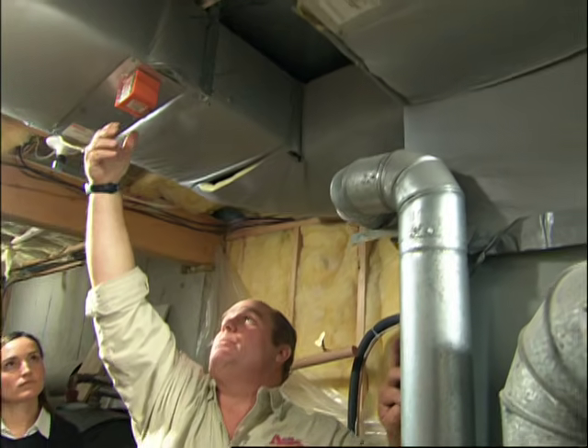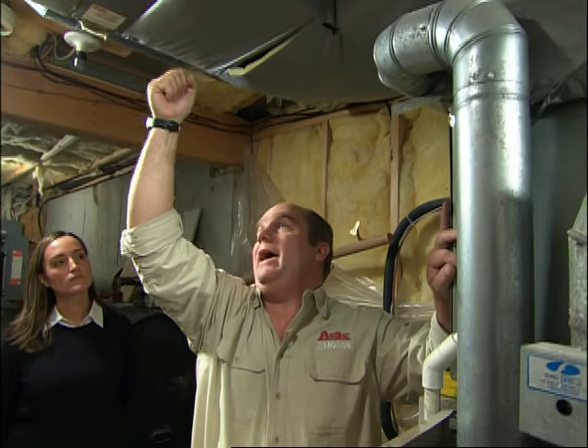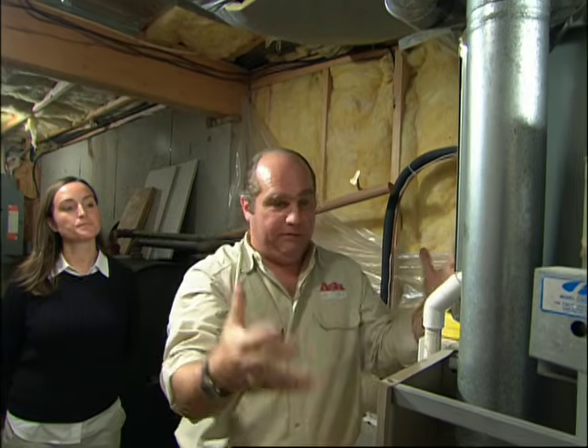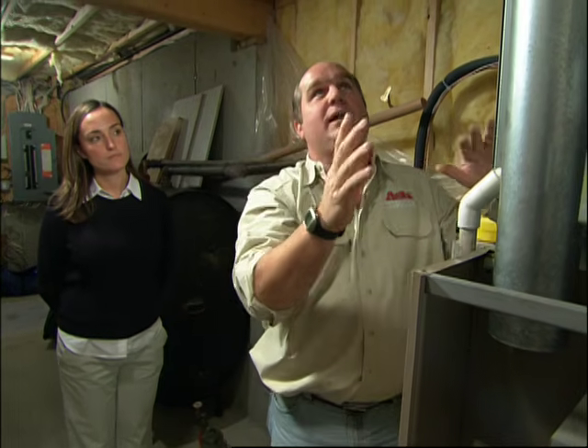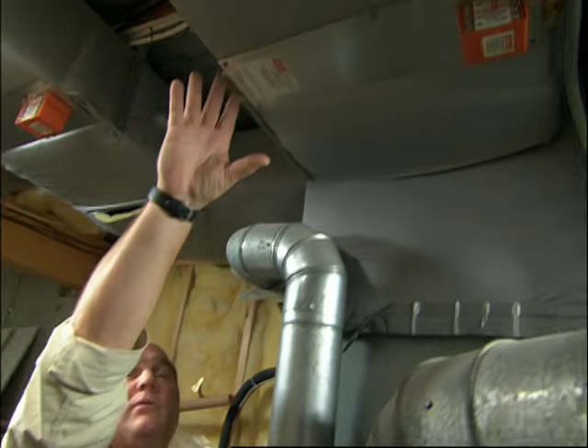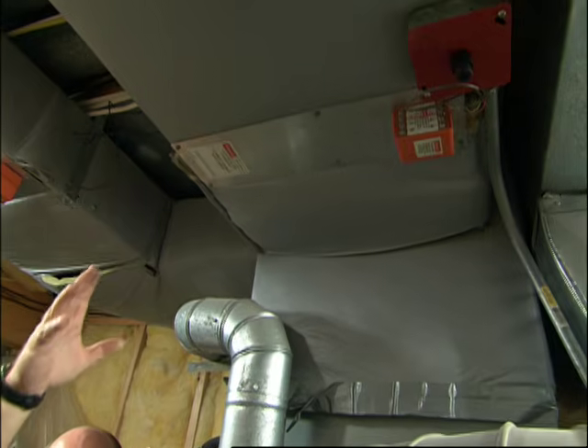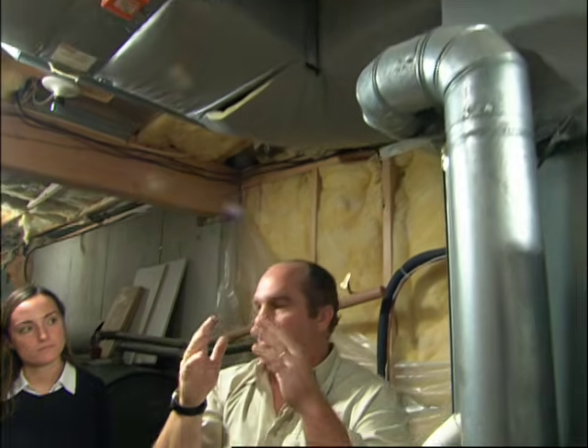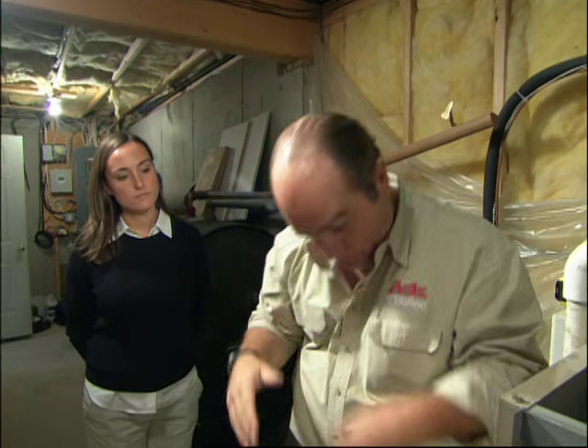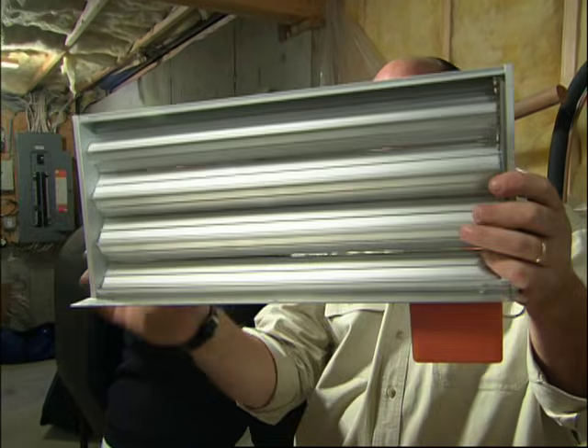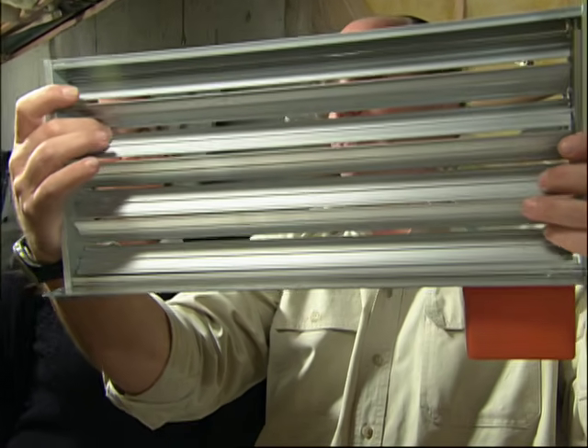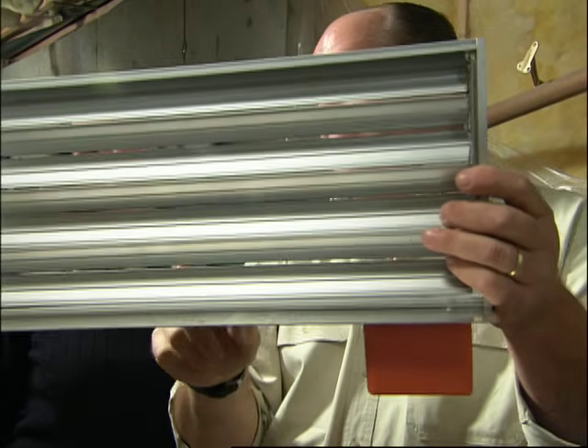Now you put this damper in, and now it's closing off half the ductwork. You got a furnace putting out 100% of its force. What happens? It's now trying to jam that air into much smaller ductwork, and it can lead to two things. One is it can build up the pressure and have a velocity noise inside the open zone, but it can also push against the closed damper. So you might get a little whistle against these damper blades right here. Okay. And that's what I think is happening to you.